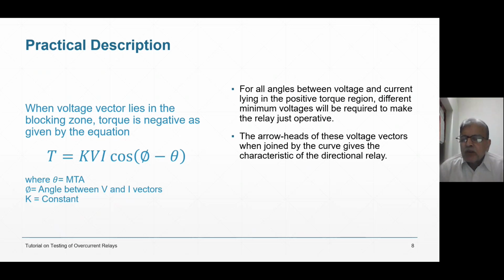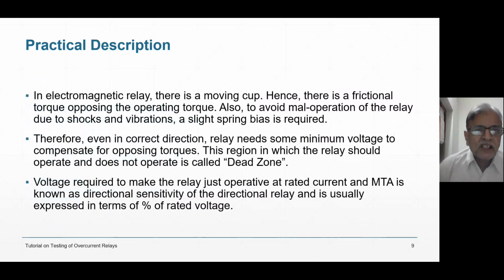For static relays, there is no moving part. For numerical relays, there are no moving parts. But that does not mean that at V equal to 0 you will operate the relay. At V equal to 0, the relay will not operate because torque is 0. So no relay has such a possibility that with 0 voltage it will operate. Try to understand, this is the basis for directional relay. Going ahead, what is the practical description? In the electromagnetic relay, there is a moving cup, as I told. Therefore, even if the direction is correct, the relay needs some minimum voltage to compensate for opposing torques, meaning frictional torque and spring torque.